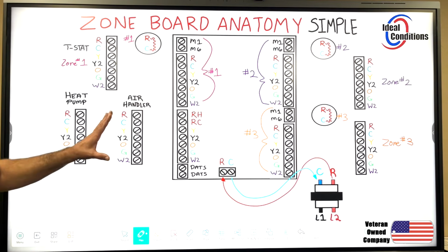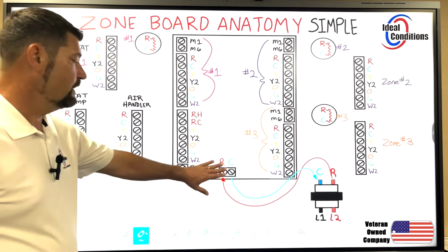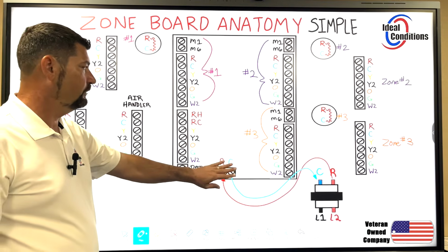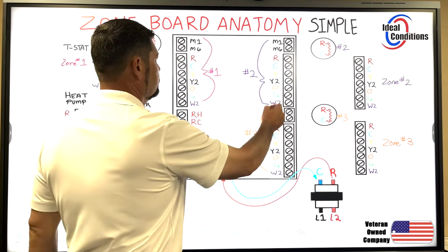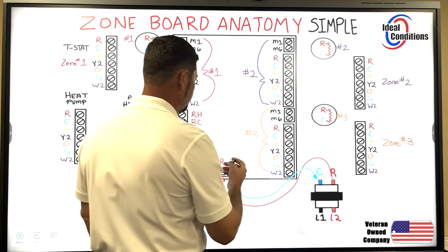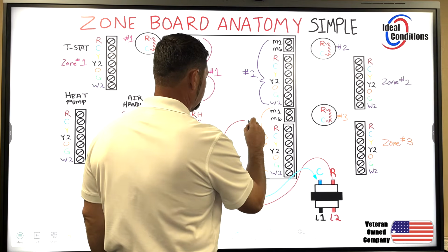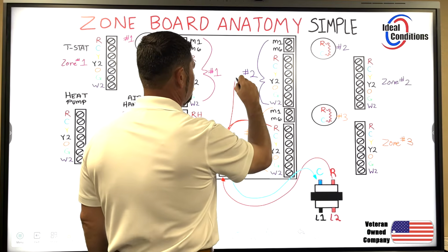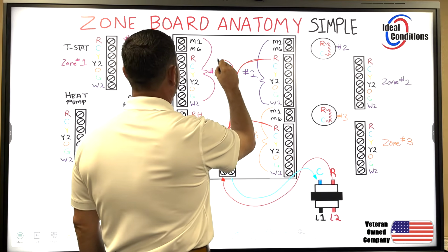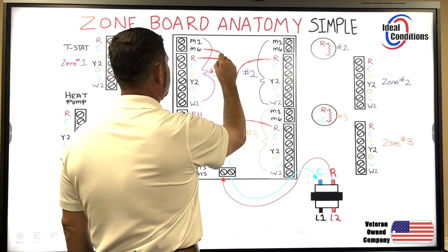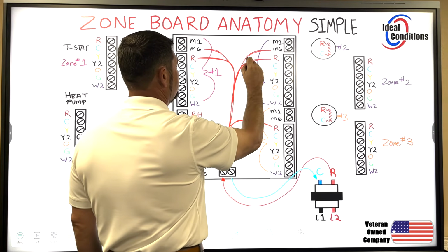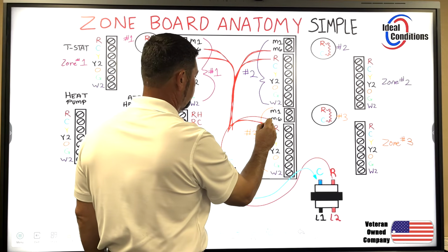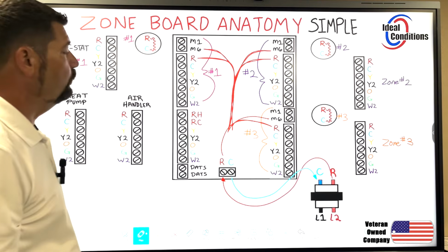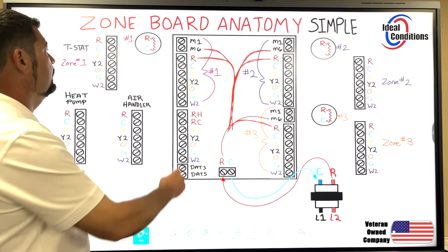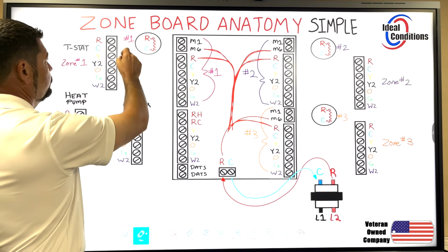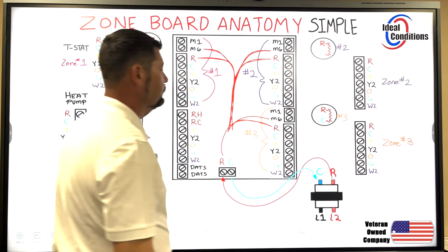And so now that we have supplied 24 volts to the zone board, none of this is going to be over here. None of it. This is only going to put 24 volts here, here, and here. So at this point, what we're saying is we're going to have 24 volts here, here, here, here on M6, here on M6, and here on M6. And that's it. And with that, then we can now energize 24 volts going to these thermostats on all 3 zones.